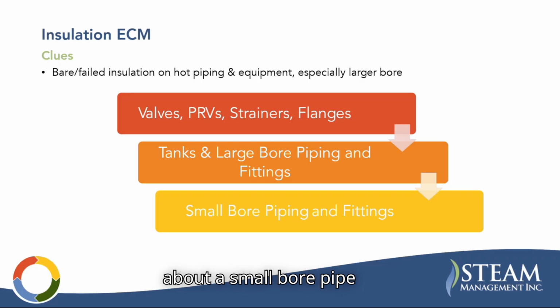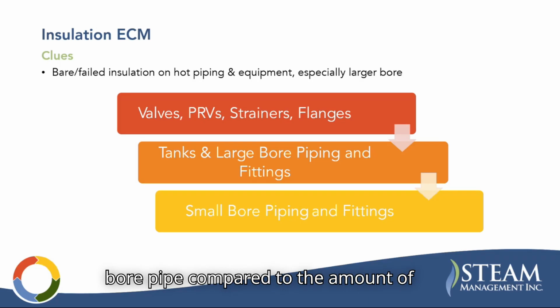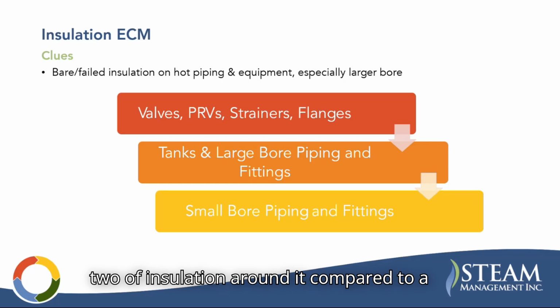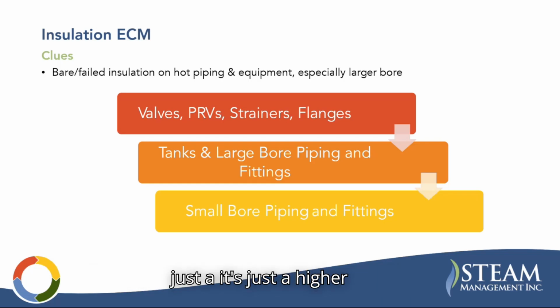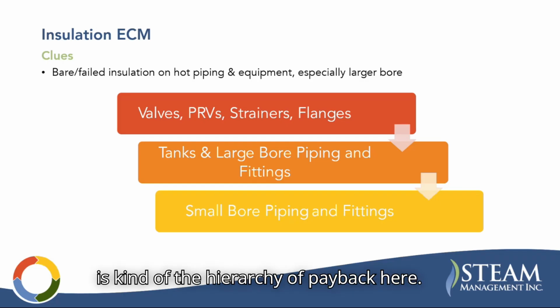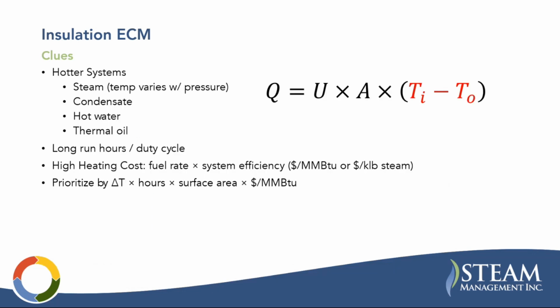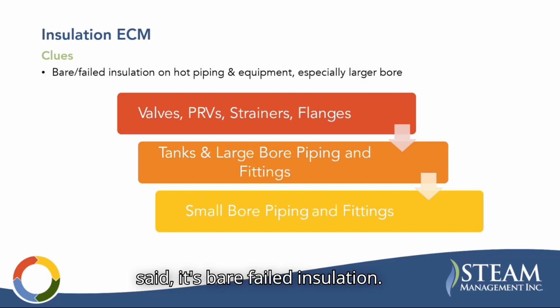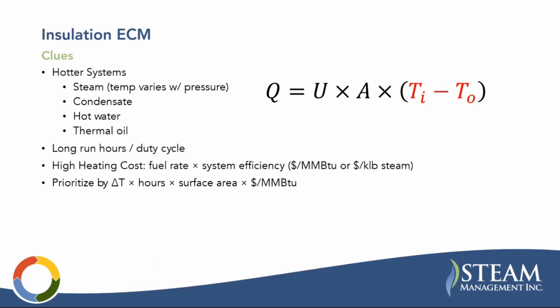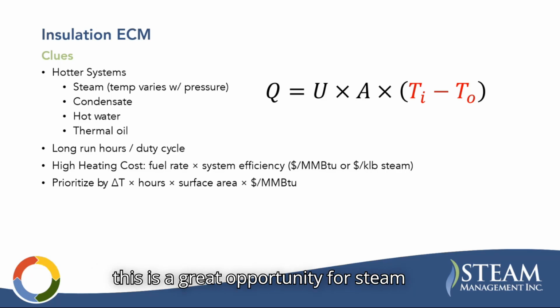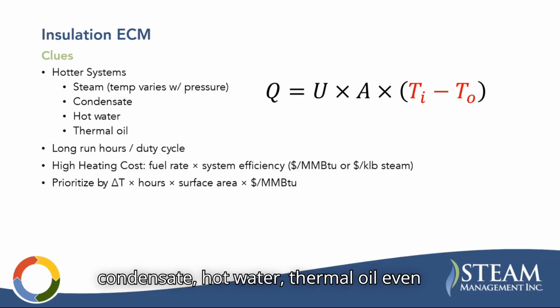So if you think about a small bore pipe and the amount of surface area on it compared to the amount of insulation when you're putting an inch or two of insulation around it, compared to a big tank or a large pipe, it's just a higher ratio. So this is the hierarchy of payback here. And the clues really are bare or failed insulation. Hotter systems are better, which is why this is a great opportunity for steam systems. I would say the payback is generally going to be better on a steam, condensate, hot water, or even thermal oil system than on a chilled water system. And that's because of this temperature differential here.